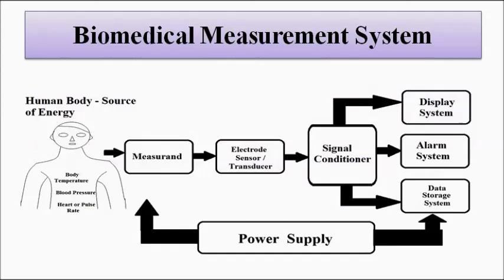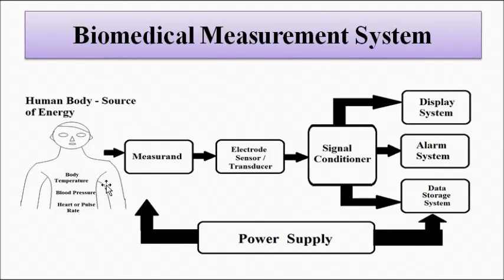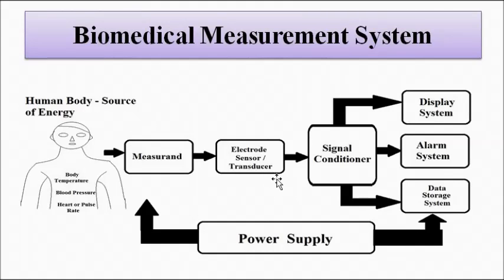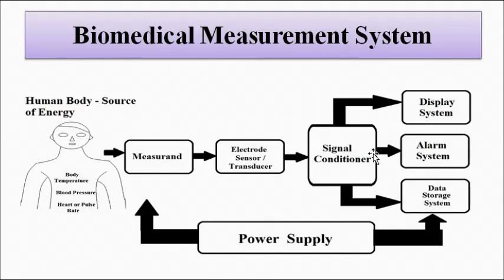A basic biomedical measurement system looks something like this. Whatever parameter we want to measure — be it ECG, electromyogram, electroencephalogram, body temperature, blood pressure, heart rate, pulse rate — we measure it with the help of a sensor or transducer placed on the electrode. After the transduction process, the measurement is converted into a suitable voltage or current signal, which is of low magnitude in the order of microvolts or millivolts. It is then fed to the signal conditioner and processing units for amplification, frequency response, noise removal, linearization, and then given to the output system for display, storage, or alarm generation.